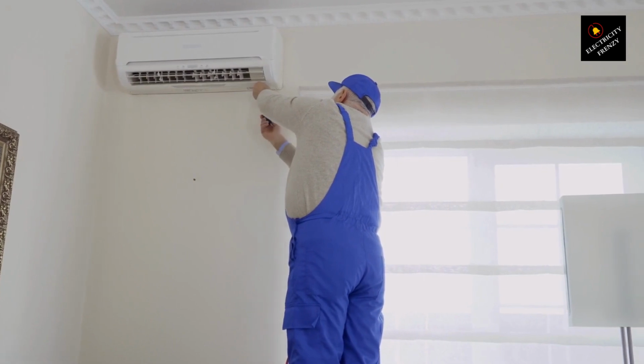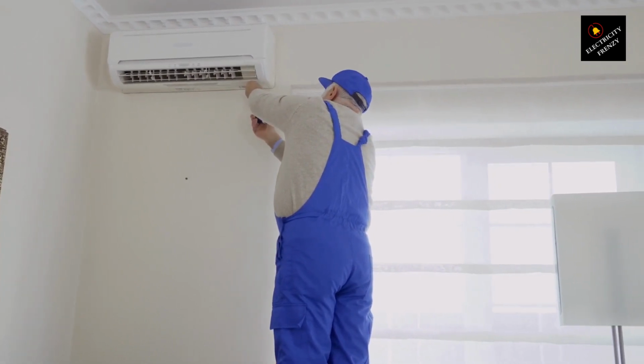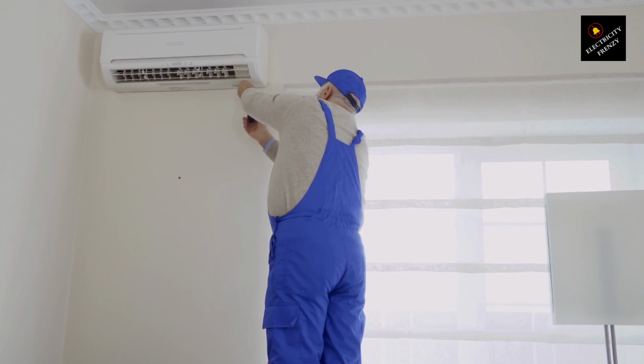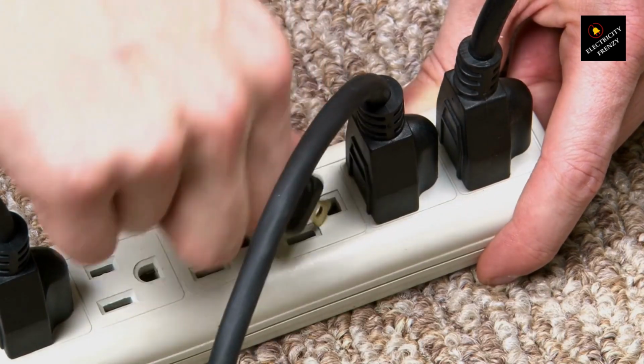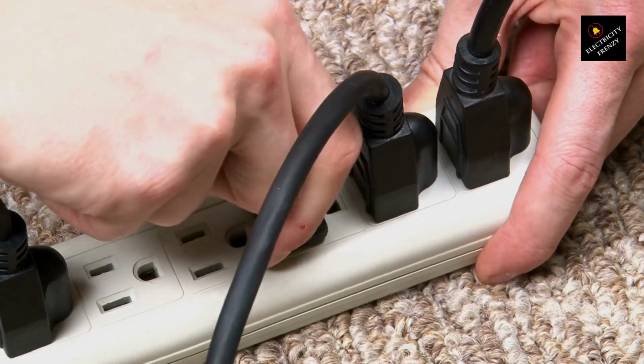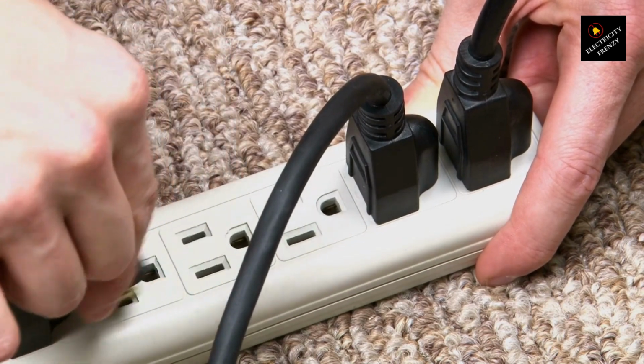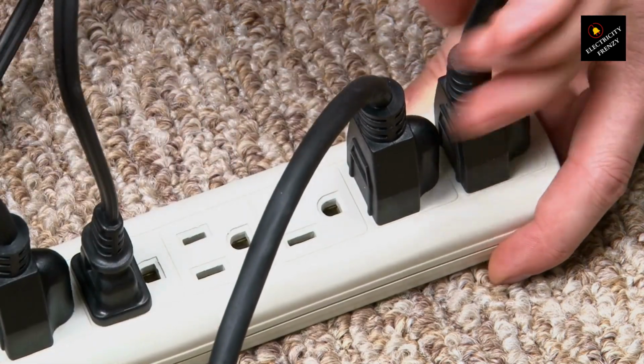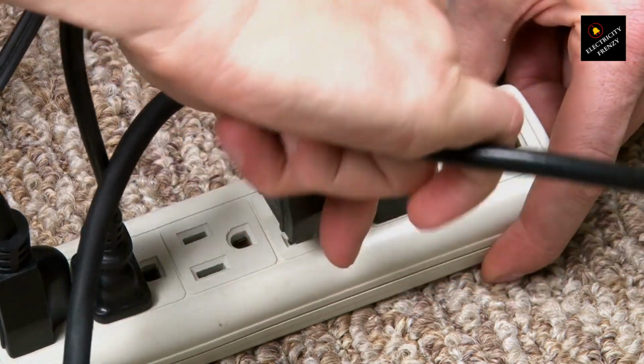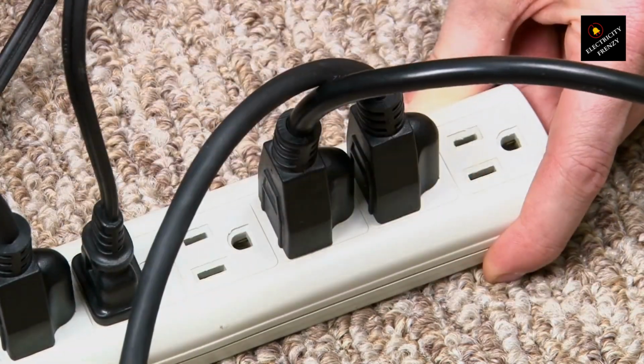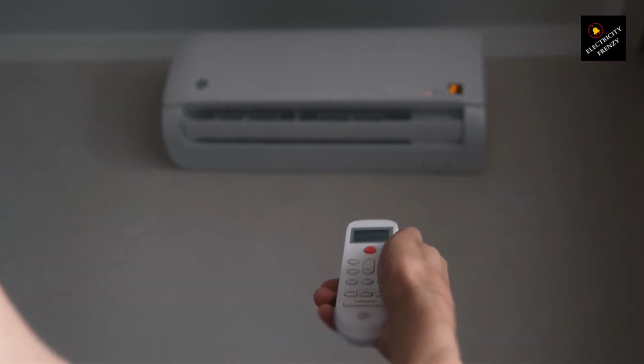When your air conditioner draws too much current, it can overwhelm the circuit and cause the breaker to trip. To diagnose an overload, you can start by checking the amperage rating of your air conditioner unit and comparing it to the circuit breaker's rating. Use a clamp meter to measure the current draw of the air conditioner while it's running. If it exceeds the breaker's rating, it indicates an overload.